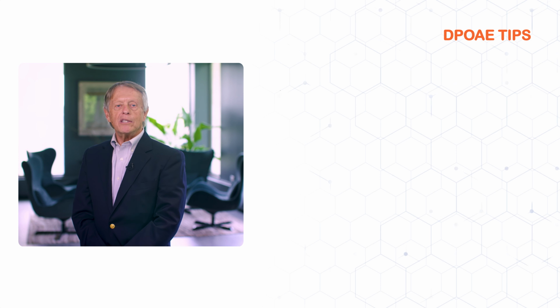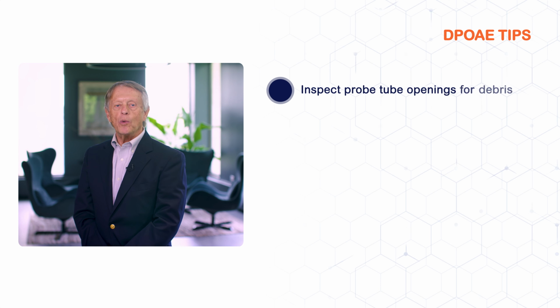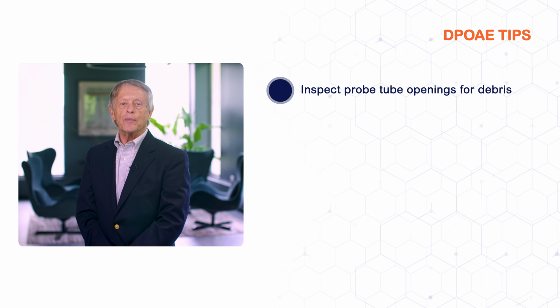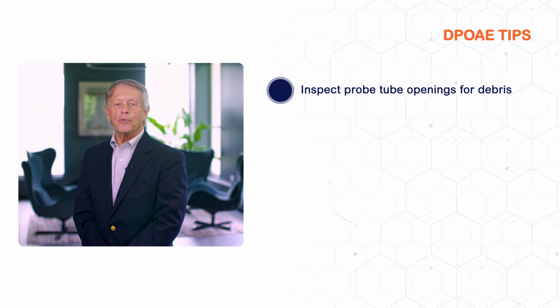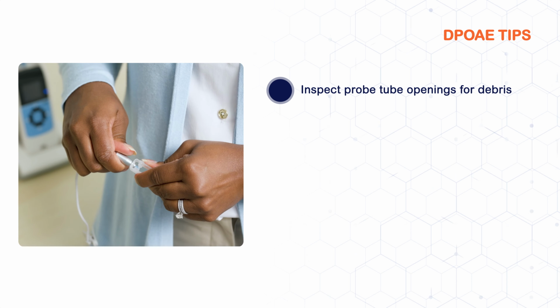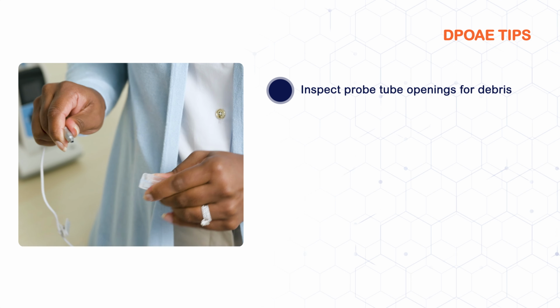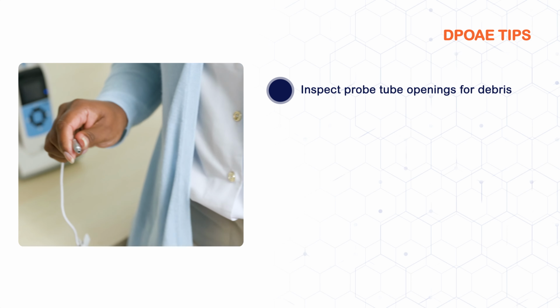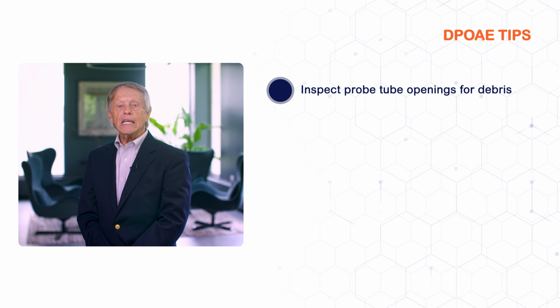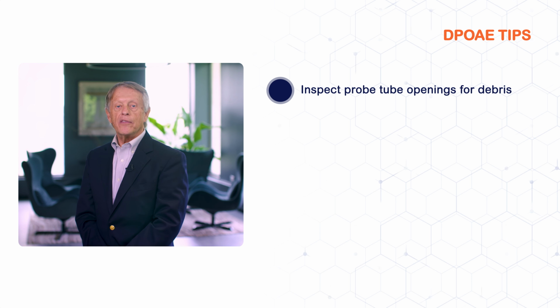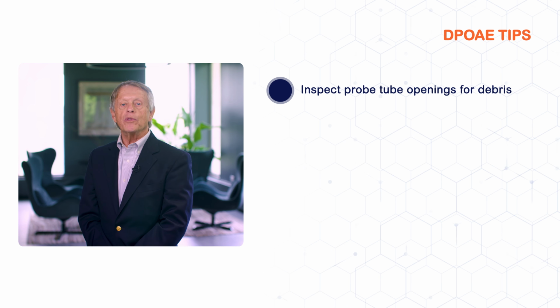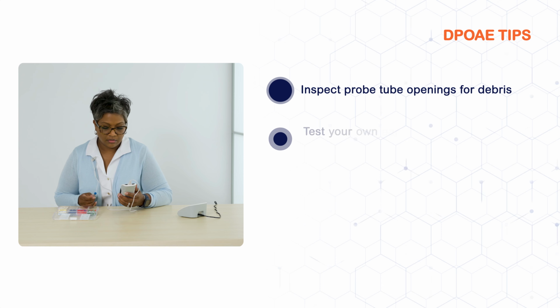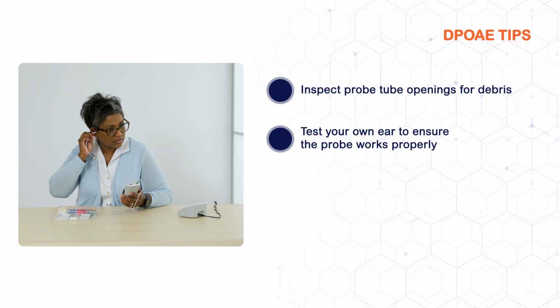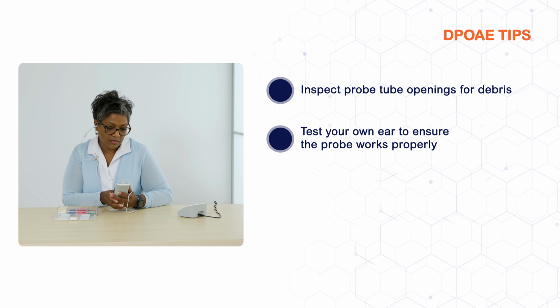Here's a handy tip. Before DPOAE screening, take a moment to inspect the openings in the probe tube on the end of the probe to make sure they're free of debris and not blocked. The Corti device comes with a probe tube removal tool and extra probe tubes so that you can easily remove and discard the dirty tube and replace it with a new one. You can also run a quick DPOAE test on one of your own ears before screening children to be sure there's no problem with the probe.